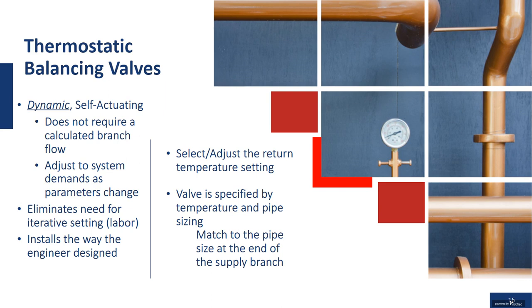I would say, and I'm sure you know this as well as I do, that over 90-something percent of the applications are either 1/2-inch or 3/4 inch. And from a temperature standpoint, it used to be 110, 120. Now we're seeing that elevate over time, where it's gradually increasing. The recirc temperatures are increasing, and maybe you're seeing that, and maybe you have customers asking you to start recircing at higher temperatures.